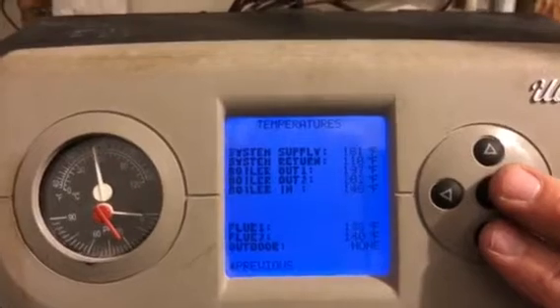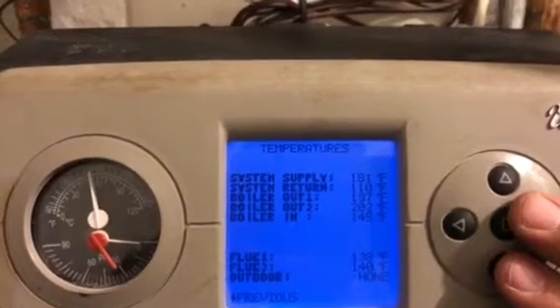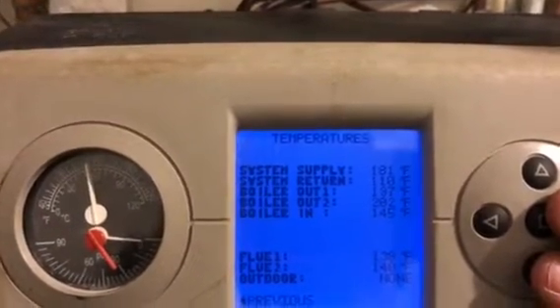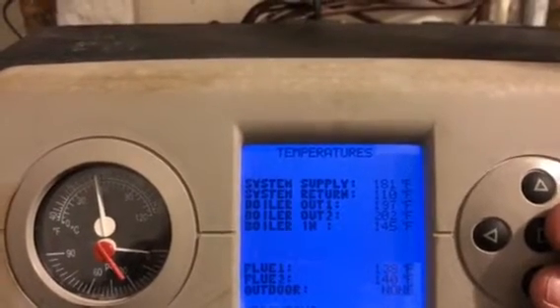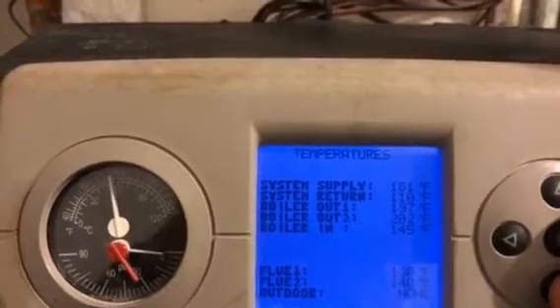We'll take a look at the temperatures — look at the boiler in and boiler out delta T. That is tremendous: 202 degrees Fahrenheit out to 145 in. Normally a Weil-McLain likes to look for a 20 degree delta T. The boiler is basically overheating.